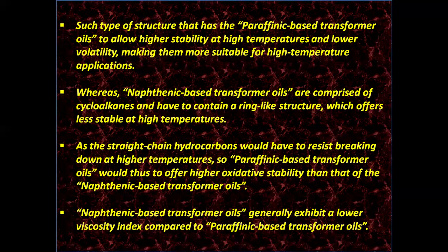As the straight chain hydrocarbons resist breaking down at high temperatures, paraffinic based transformer oils thus offer higher oxidative stability than that of the naphthenic based transformer oils.